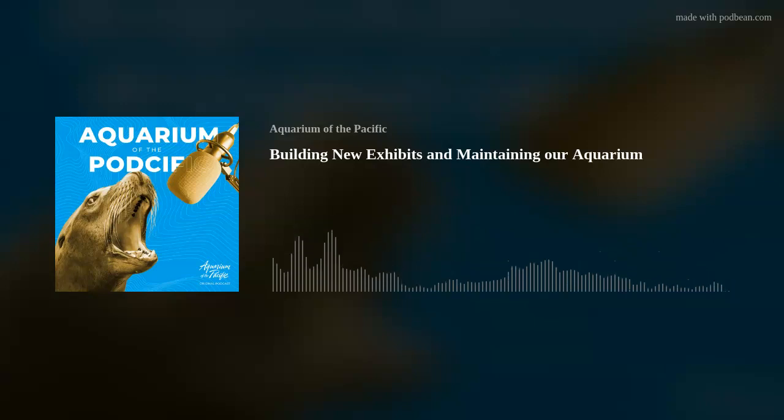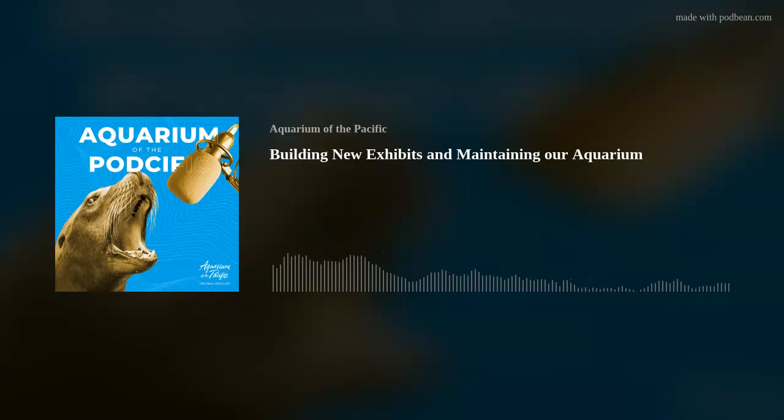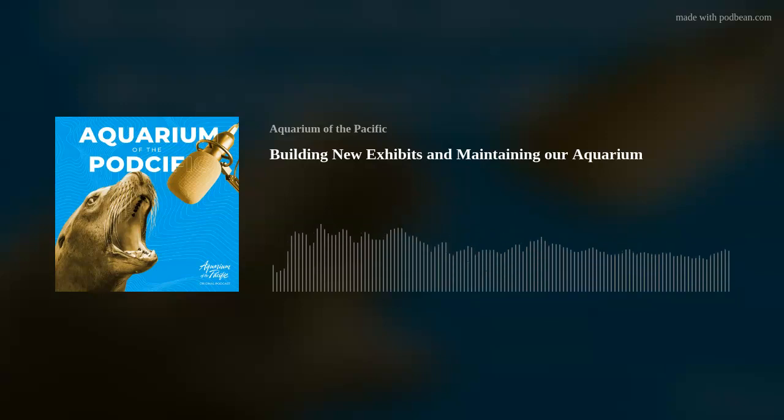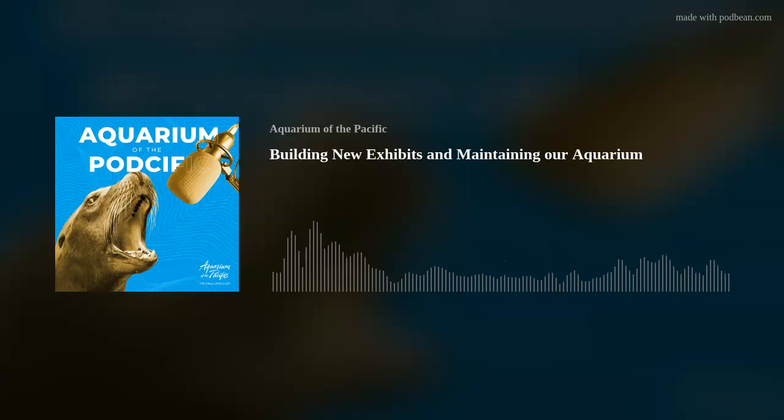All the northern galleries are 300s. All the SoCal galleries are 200s. Does mountain frogs have a number? No. We just call them mountain frogs. MYLF1, MYLF2. Those correspond to points on our Siemens server, our computer and monitoring system. So we can't, I guess we can, but none of us want to type out tropical reef filter flow, which is one of the things we monitor all the time. It's 443, so we get a notification if there's an issue. It will say something like FF4430, which means there's no flow going through tropical reef. It means there's something wrong and we need to go figure out why.